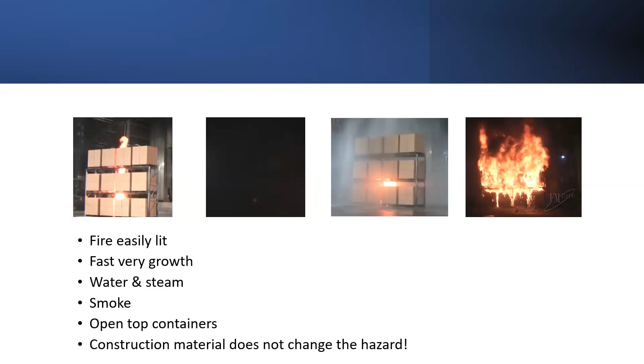And I believe the newer systems are not using so much plastic in their totes, in their boxes. They're going over to metal boxes, which is great. And that's definitely going to help. But they still have all the materials that are stored in them at 4 times the traditional density. So the fire load is still high. And these boxes will still capture the water. So it does not change the hazard.